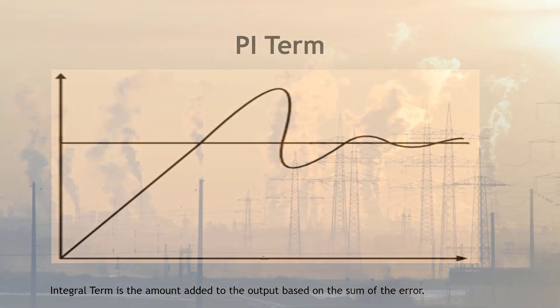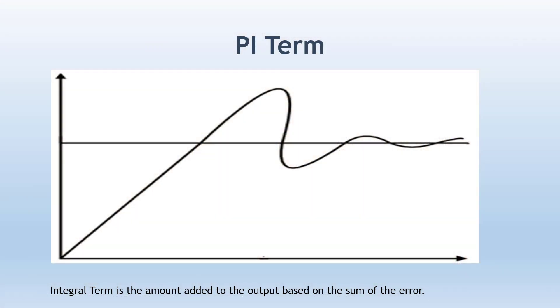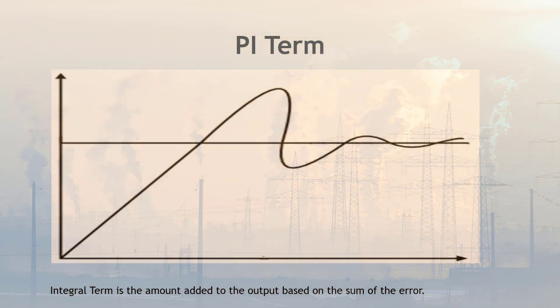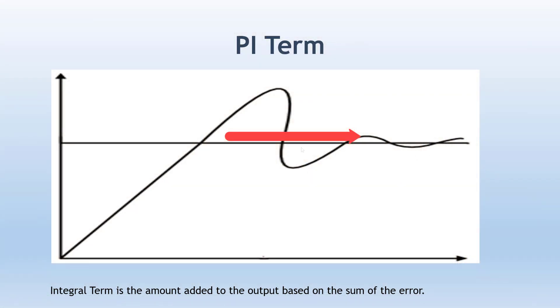Along with P, you need to have the I term as well. Integration means sum up — the integral term is the sum of errors. It is not talking about the current error; it is talking about past errors too, summing all of them up. Based on that, the integral term is added to the output to take care of all past errors and achieve better control. When you introduce the I term, you would see the process variable get back to the set point very quickly, with the deviation between set point and PV getting smaller.